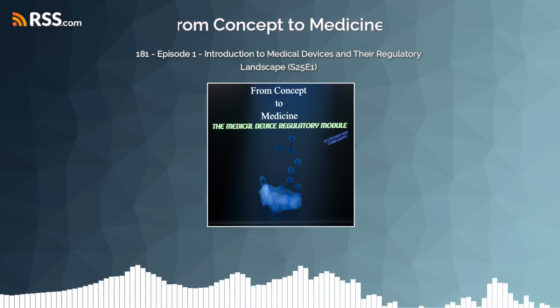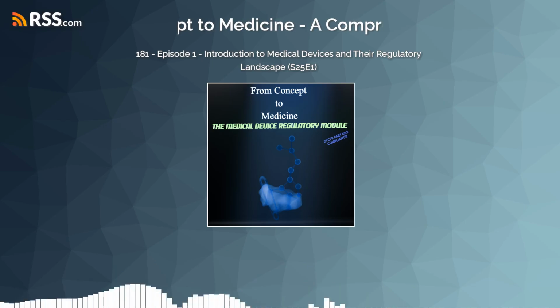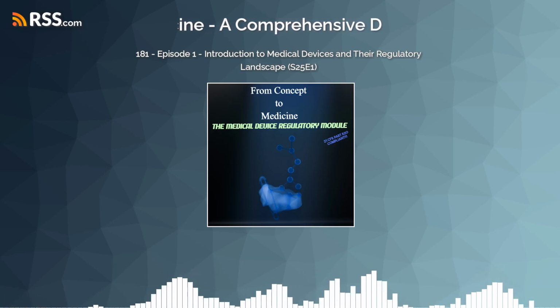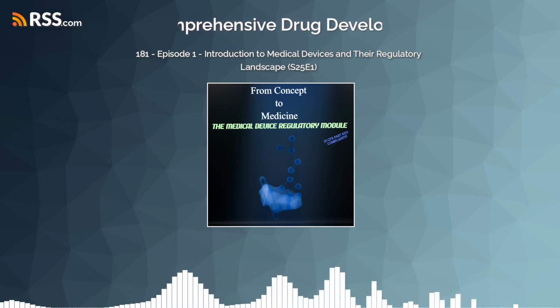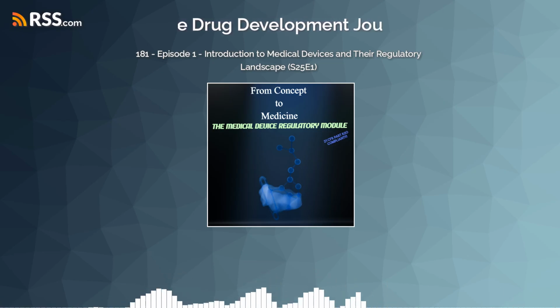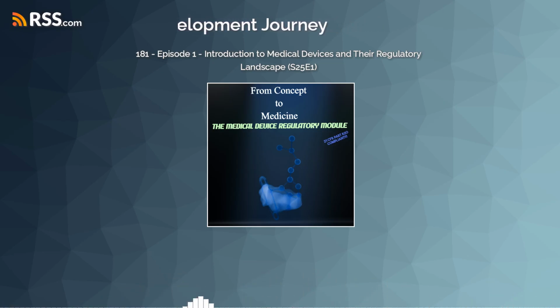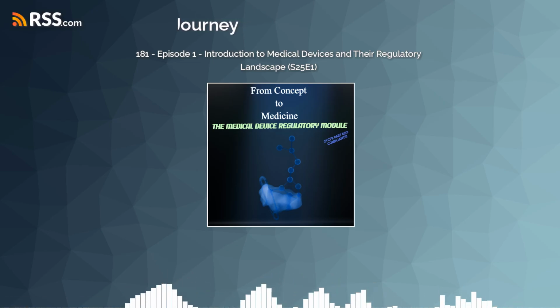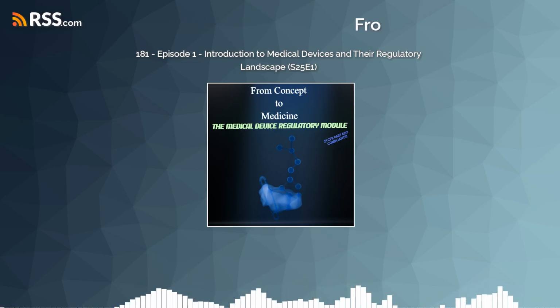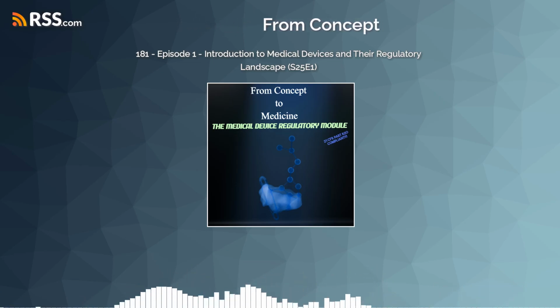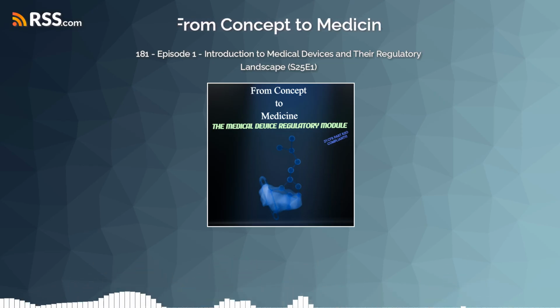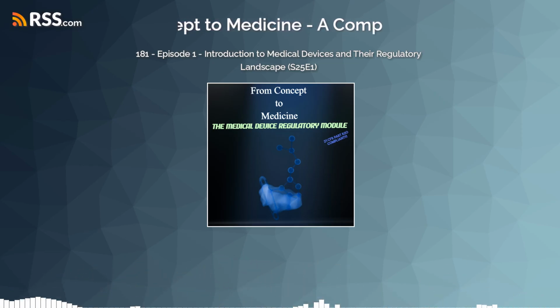Special controls. Can you give an example? Like, what might that actually involve? Sure. So, for instance, for an oximeter, a special control might be a mandatory performance standard dictating its accuracy under various conditions, or maybe specific labeling requirements, or even a requirement for post-market surveillance, like tracking patient outcomes. Okay, so more tailored oversight for specific risks.